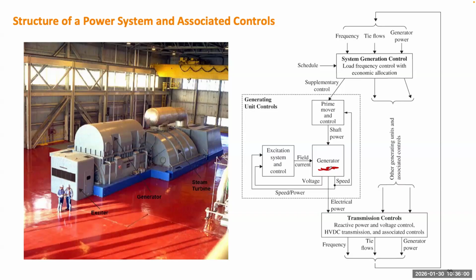So we can use the equations for a dynamic stability study. And we also briefly talk about the load of the generator, how we can model the load, whether it's a dynamic load or a static load. So we'll cover both. In the second part, we'll focus on modeling these two blocks and the related frequency and voltage control. Okay. So this part is just the prime mover and the control, including the turbine and the governor models. We'll model those elements in detail, and then we talk about how to do the load frequency control from the system-wide view. So that's the frequency regulation section.